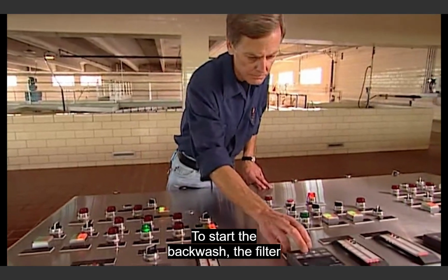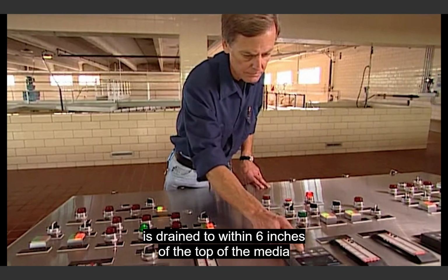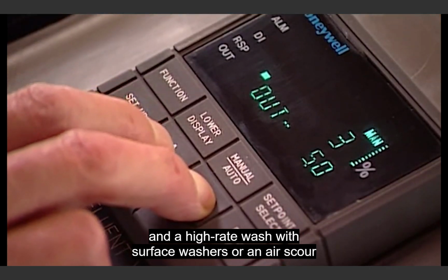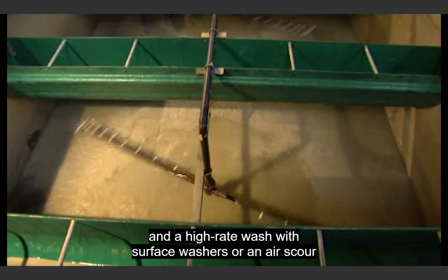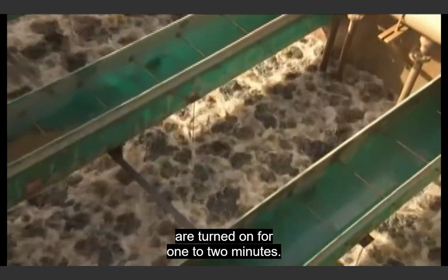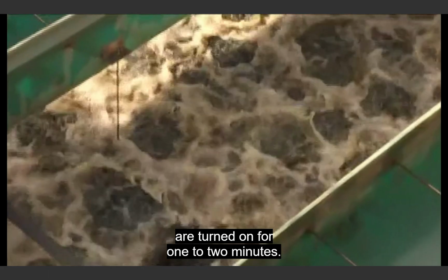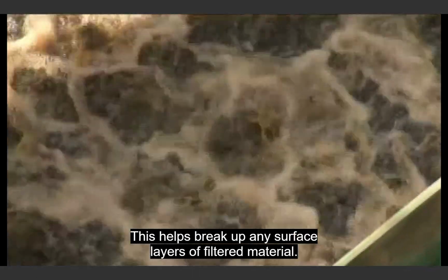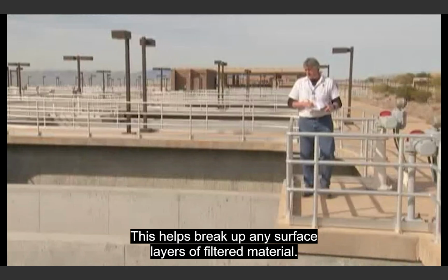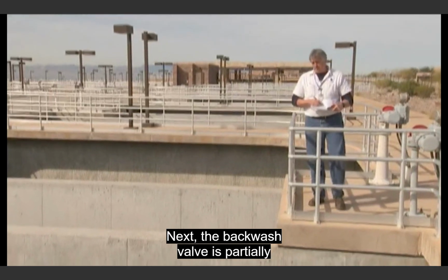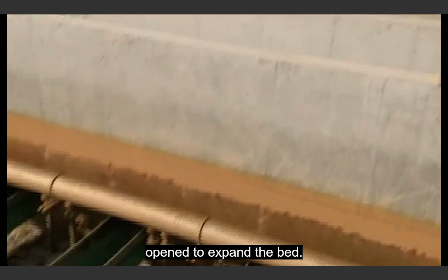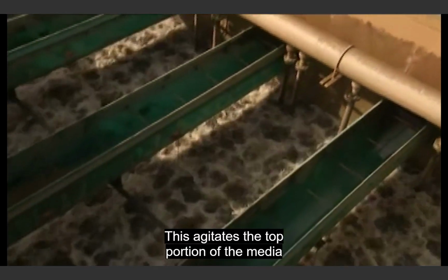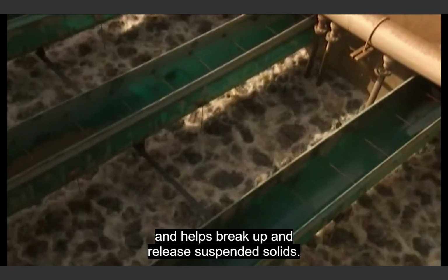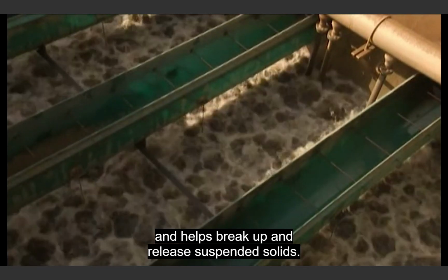To start the backwash, the filter is drained to within 6 inches of the top of the media, and a high-rate wash with surface washers or an air scour are turned on for 1 to 2 minutes. This helps break up any surface layers of filtered material. Next, the backwash valve is partially opened to expand the bed. This agitates the top portion of the media and helps break up and release suspended solids.